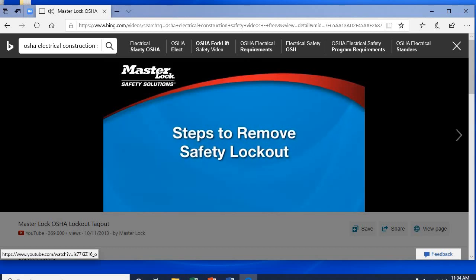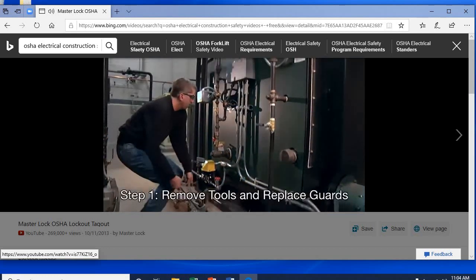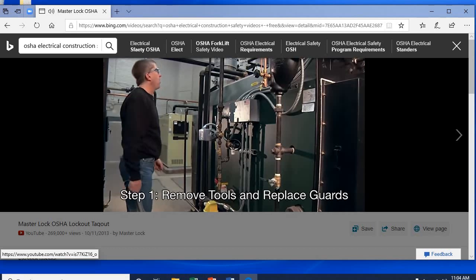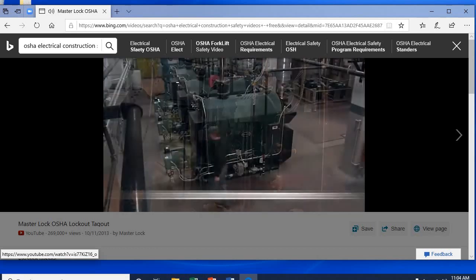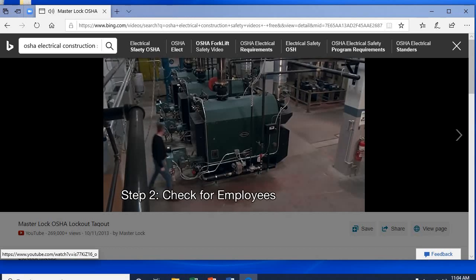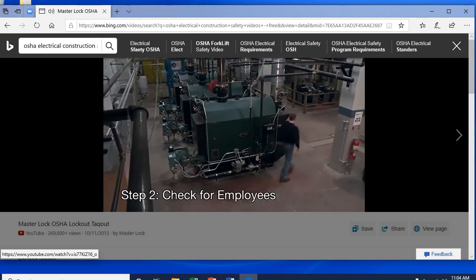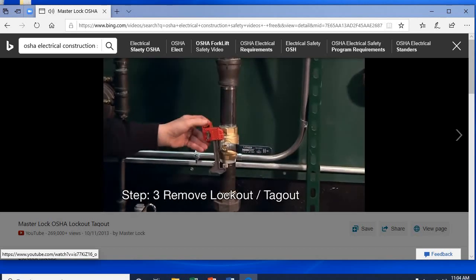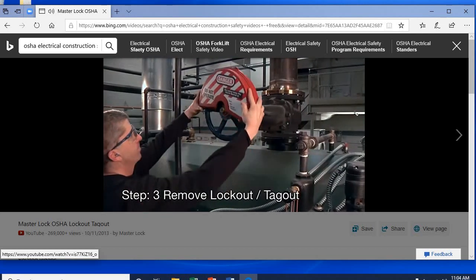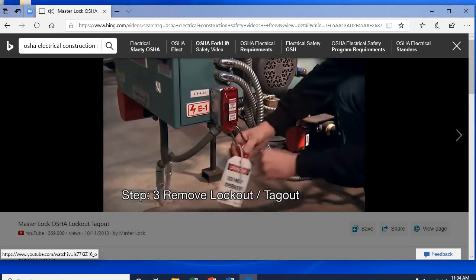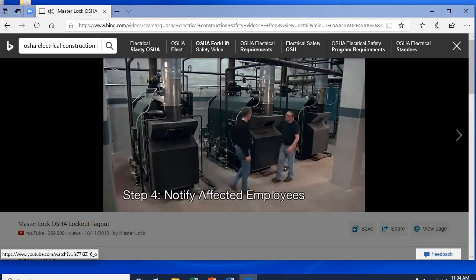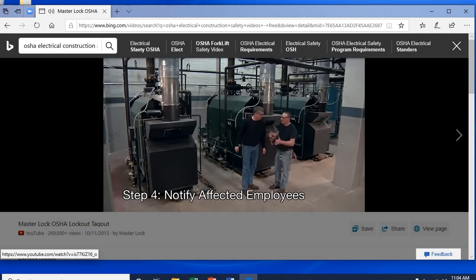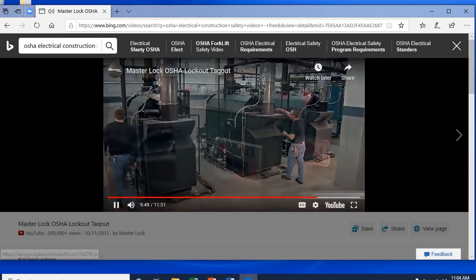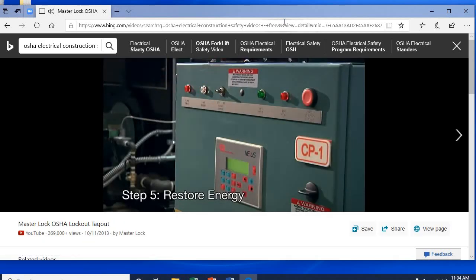After the service work is finished, there are 5 steps to release the equipment from lockout-tagout. First, make sure all tools have been removed and all machine guards are back in place. Check that all employees are clear of the machine. If you can't see inside a piece of equipment, take a head count. Remove the lockout-tagout devices. Each person must remove his or her own lock and tag. Before you restart the equipment, notify all affected employees that the lockout-tagout devices have been removed. And finally, restore energy to the equipment in the order indicated by the lockout procedure.